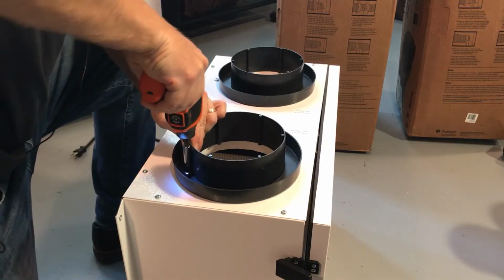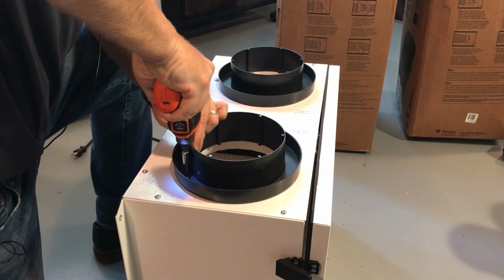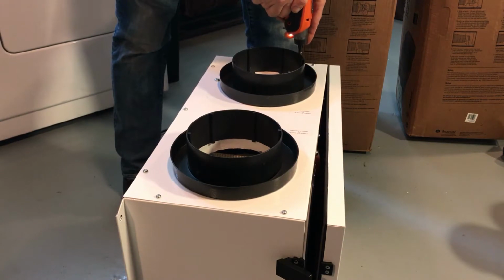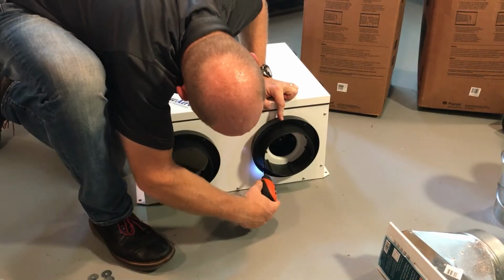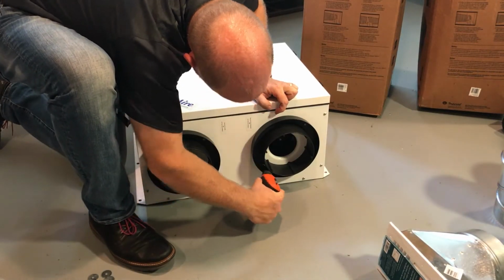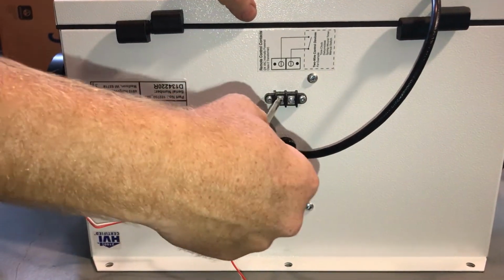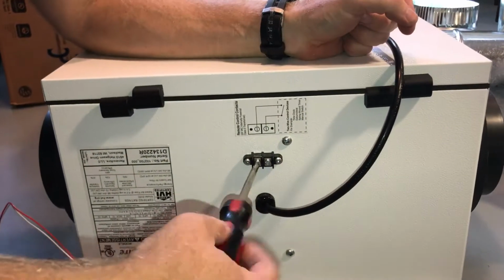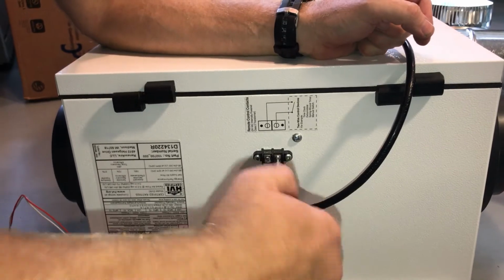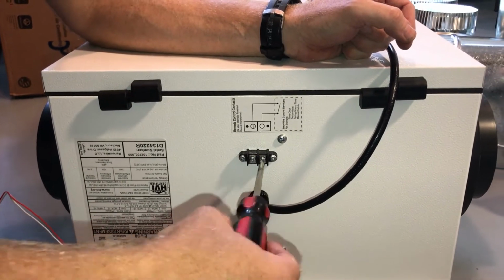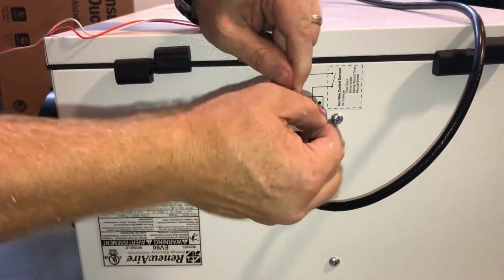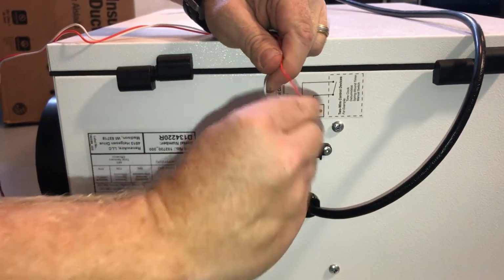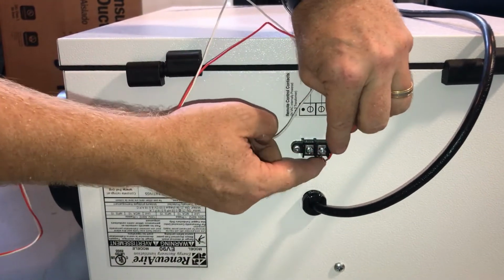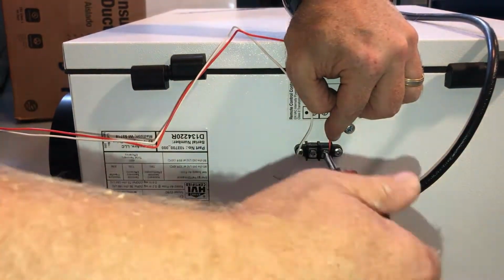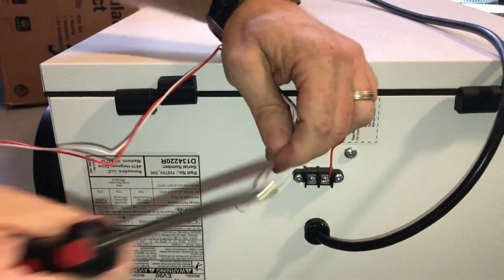Before we hang the ERV on the wall, it's a good idea to go ahead and connect these 4 duct connectors, and then go ahead and connect your wire right now to those 2 screws. This is 18 gauge thermostat wire that you're using, and just go ahead and get it connected now because it's a lot easier to do it now than doing it after you have hung the unit on the wall.